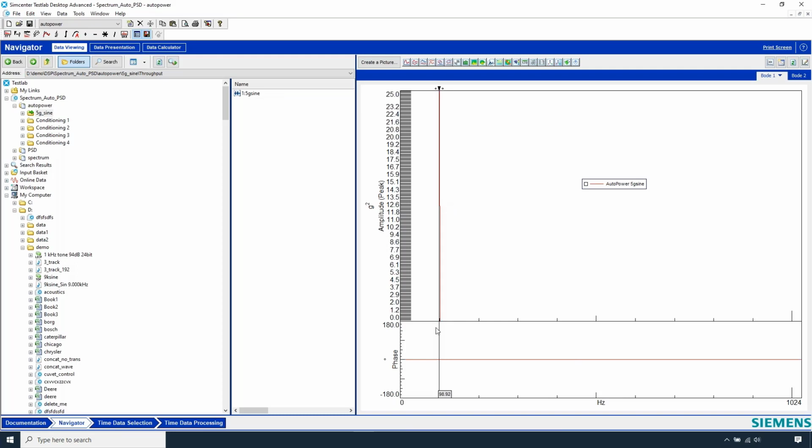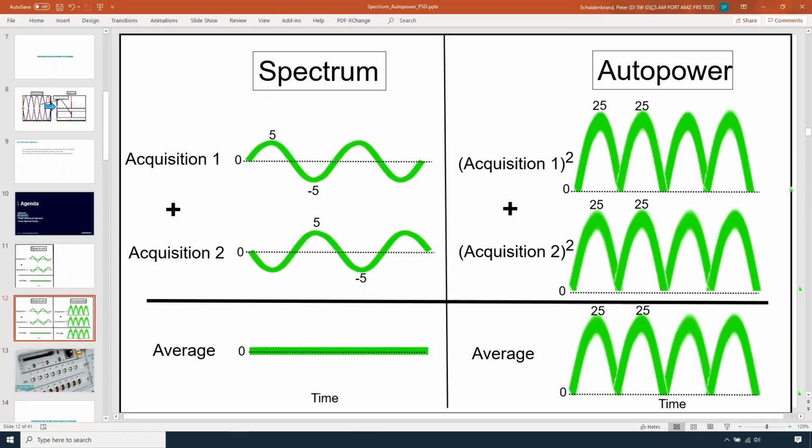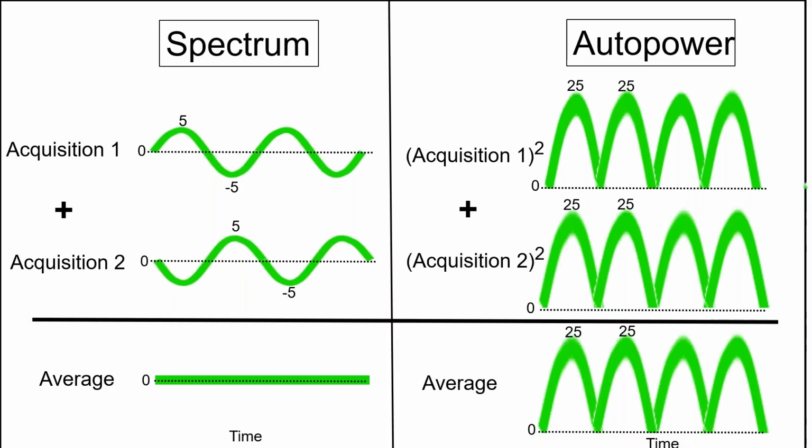But there's a few things about this sine wave. The first thing is, is it 5 G's amplitude here? No, it's squared. 25. Yeah, it's squared. It's 25 G's in amplitude, which is kind of funky. But by squaring it, what did I successfully do? It looks like the phase is 0 now. It's eliminated. It is 0 across the board because it's an all real function by squaring it. So I eliminated the phase problem, but now I'm left with 25 G's squared. Is that good? Depends on how you like to look at your amplitudes.